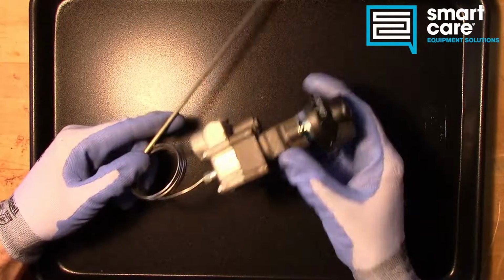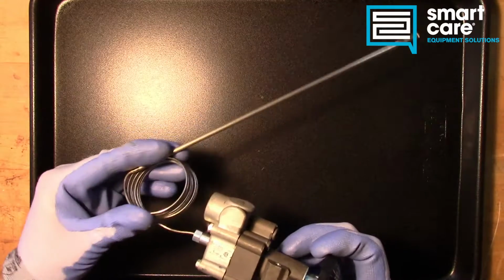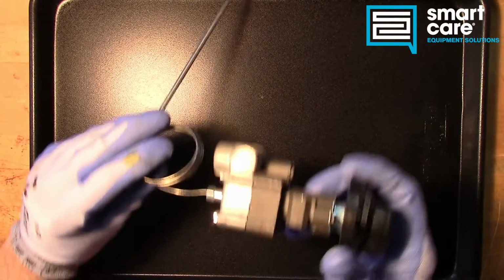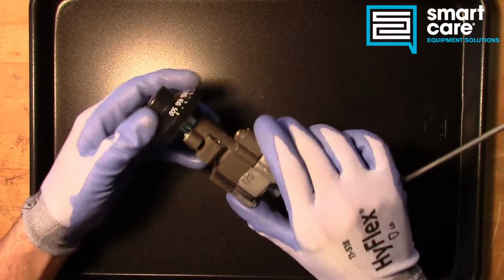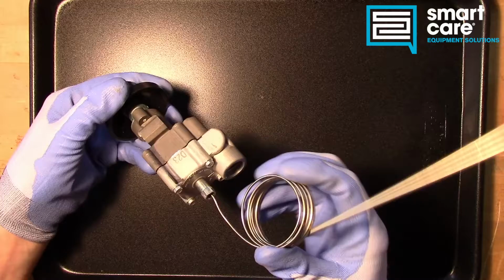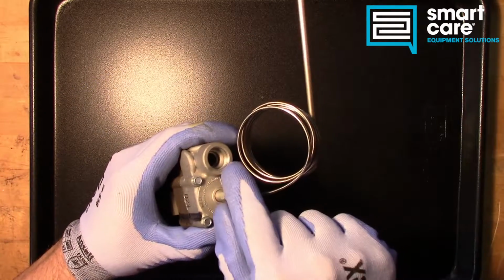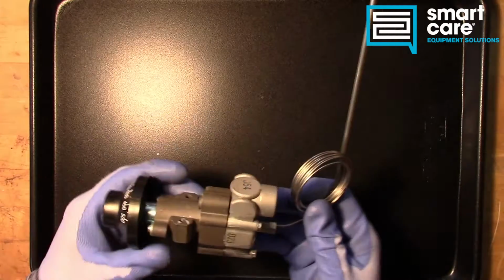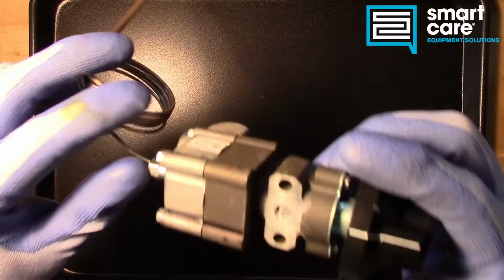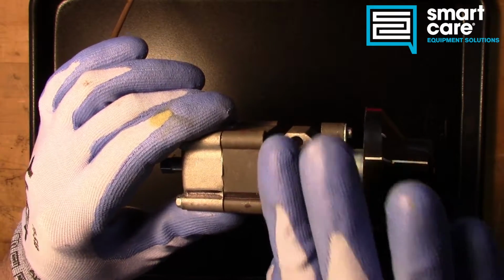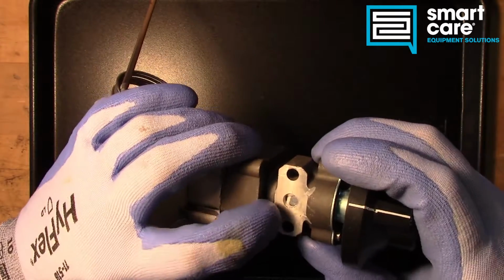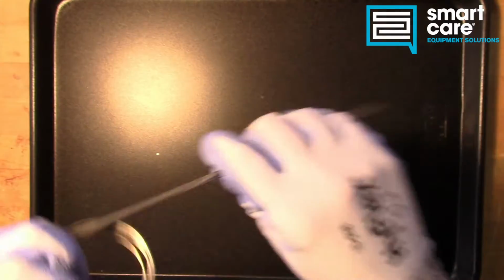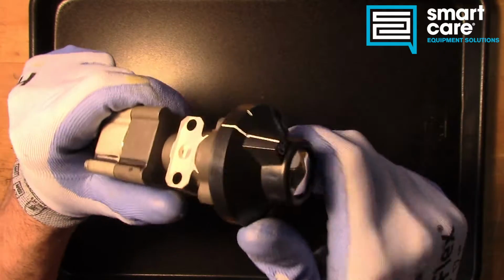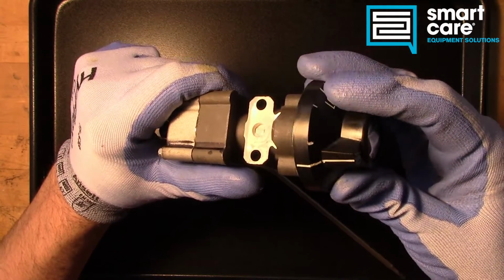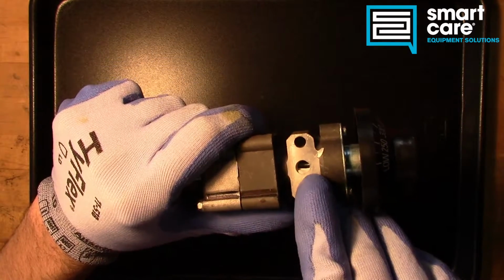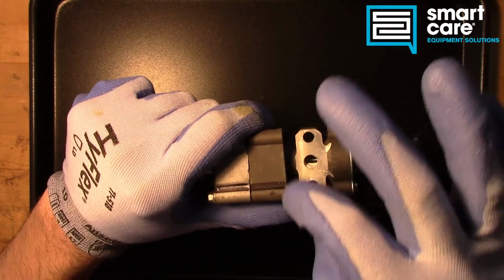This particular thermostat is new and uninstalled. You can see it's still coiled up here, but it was damaged in shipping and returned. Somehow it ended up back at our training center for us to use as an example. But you can see from the coil on here and the clean threads that this particular thermostat has never been installed. So let's talk first about how it's supposed to work. The gas inlet is here, and there's a little adapter plate that bolts on with a gasket, and the gas flows into this opening. Now in this particular thermostat you can see it's turned off, but as we start to rotate that around and we get to the low position, you can see we've got an opening here so the gas can flow into this part of the thermostat.